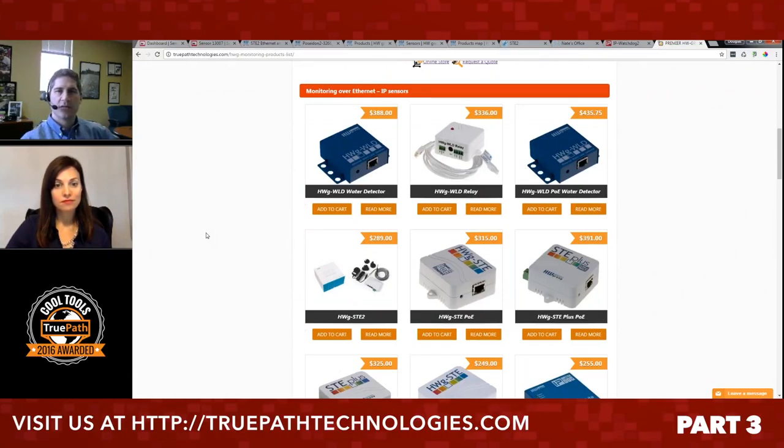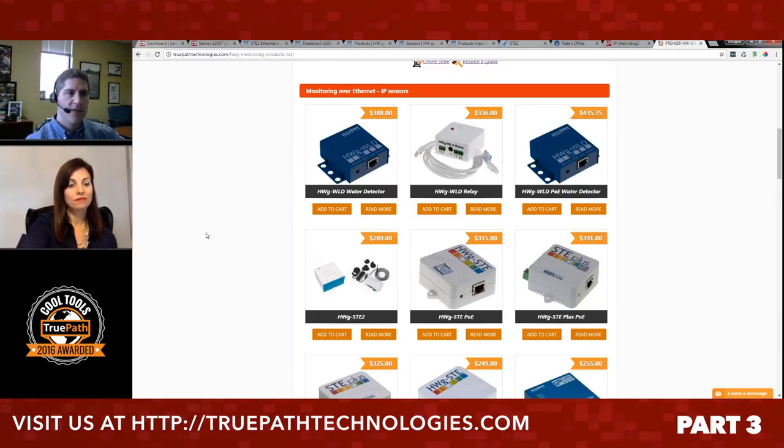This is their sort of flagship product — the P2 4002. This thing can do 12 dry contacts, it's got four relays, and it can do 16 sensors. This is really the everything-and-anything kind of device. We have some local telecommunication companies that have standardized on this so that every one of their data centers and telephone rooms has one. So when they have a generator, low fuel, on battery, running out of battery, water detection — it's a standard because they see the importance of that kind of monitoring. We even have reseller discounts — we had one company putting air conditioners on top of locations like Chipotle, monitoring whether the air conditioner was on, if it was leaking, how much power — they chose the HWG line and integrated that product into their solution.